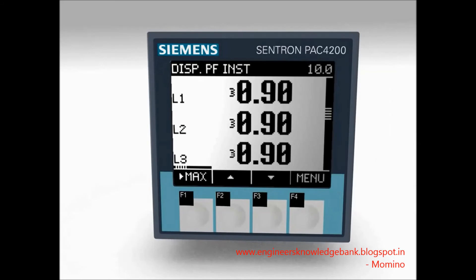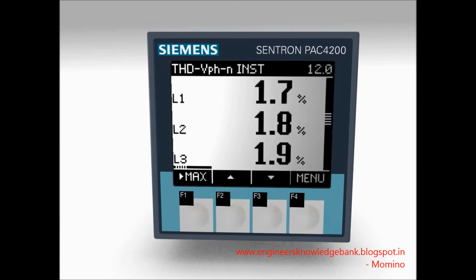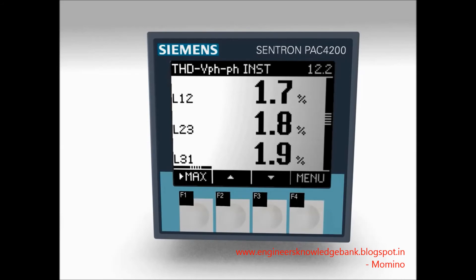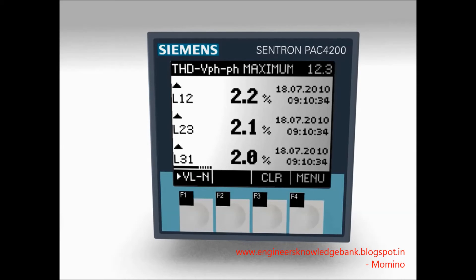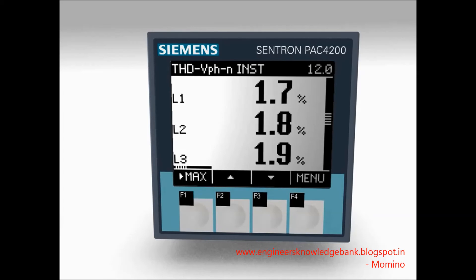The measuring device SENTRON PAC4200 records the system's load curves over a period of 40 days. These load curves can be evaluated with the energy management software Power Manager. The network quality monitoring function ensures high availability, as excessive harmonic currents would lead to a reduced system service life or early tripping of the protective equipment.